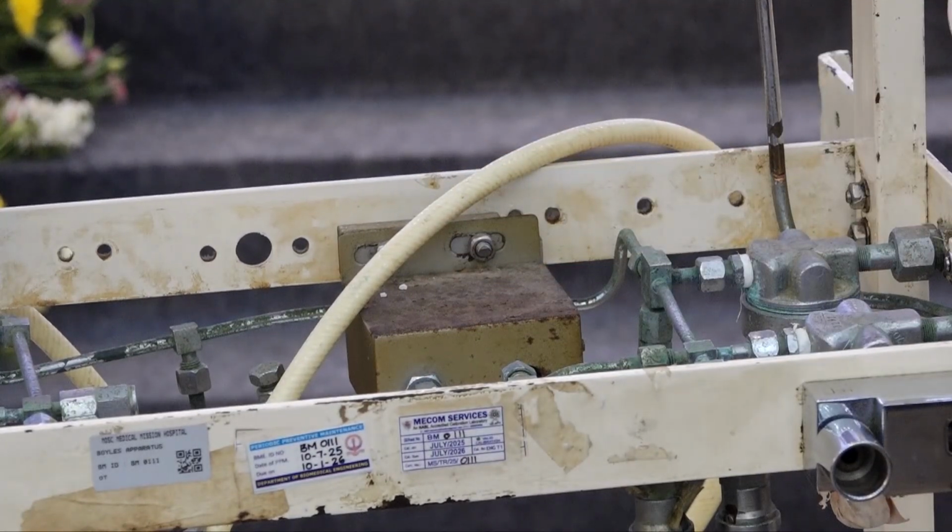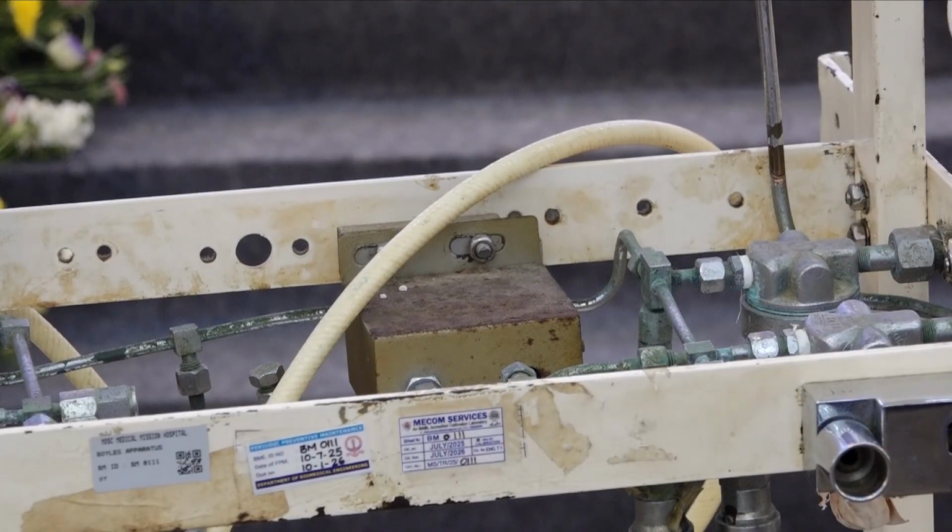So these electronic alarms, which are also there in these machines, have both audible alarms and visual alarms. Once the pressure comes down to 30 psig, whether it's a Draeger or the GE system, the alarm will start and it will continue till you open a backup source of oxygen. So that is another part of the intermediate pressure system.